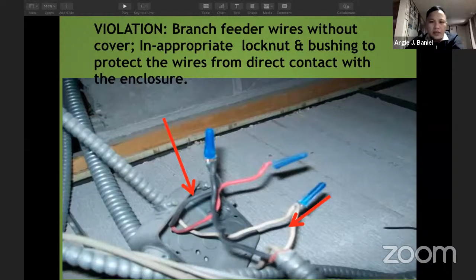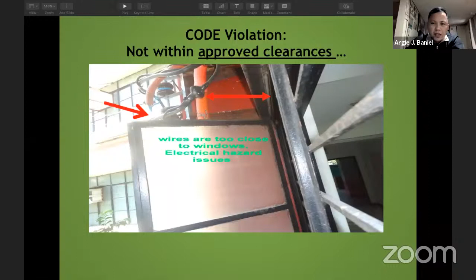Violation. Okay, branch feeder wires without cover, inappropriate lock nut and bushing to protect the wires from direct contact with the enclosure. Code violation. Not within approved clearances. That is a code violation. Wires are too close to windows, an electrical hazard. Especially if it will be used as a fire exit, there is the 10-feet rule. The electrical hazards from the window, if it is used as a secondary fire exit, must be at 10 feet away.